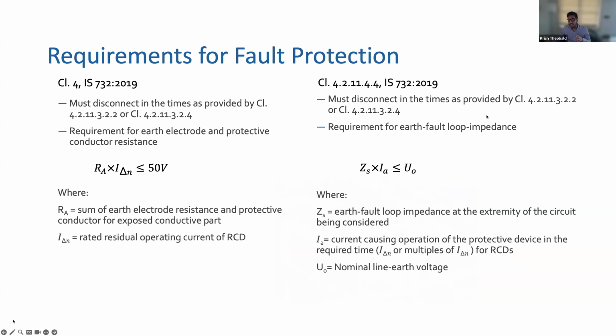I will not recommend you use an RCD here, because if you use an RCD, there are still other problems that may arise. For example, you may have an intolerable voltage drop, or your short circuit impedance will be exceeded and you have an issue with fires. The main reason is in a TT system, you need an RCD to provide fault protection, because there's no metallic fault loop, so there's not enough current to cause an MCB to trip in the event of a line to earth fault or a line to exposed conductive part fault. That is when you need an RCD.